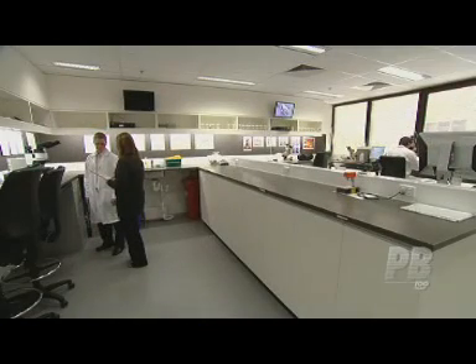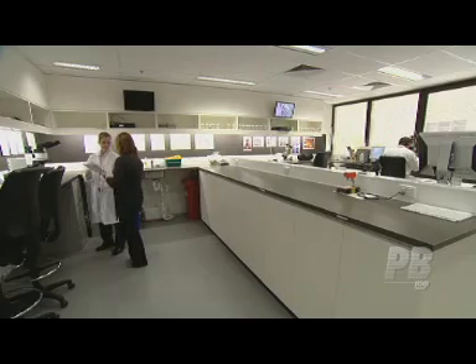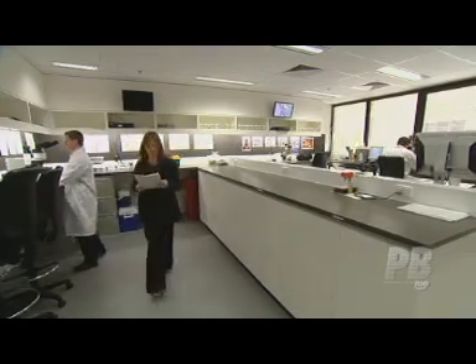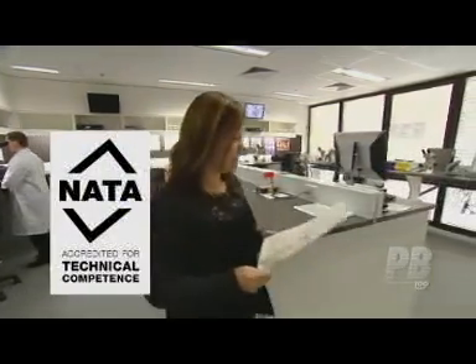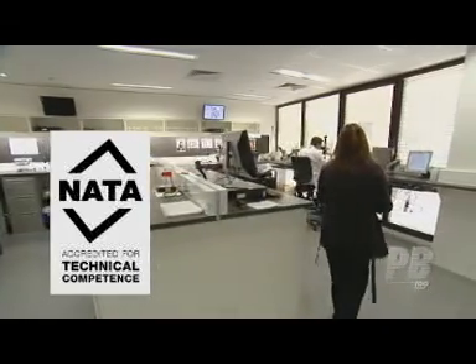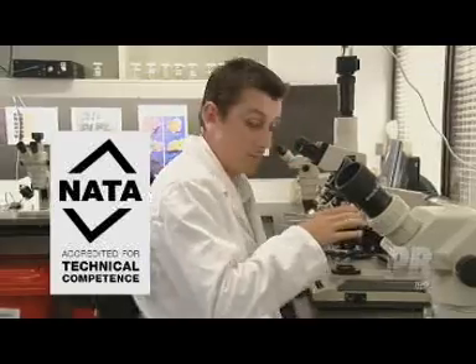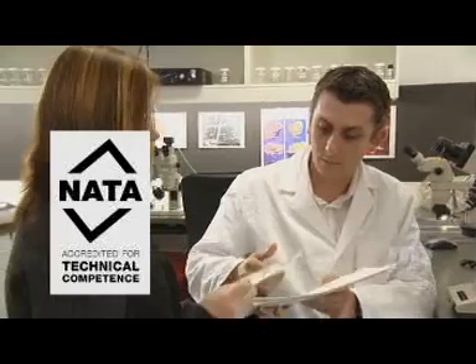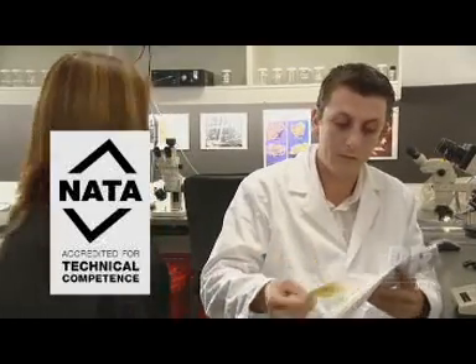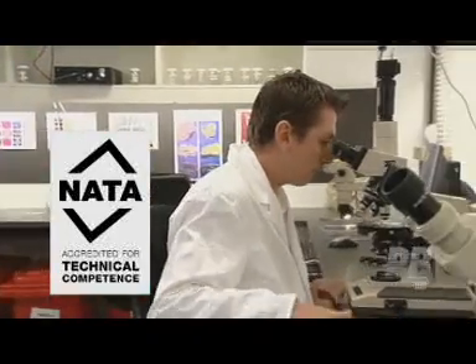To be certain test results are reliable and consistent, the sample analysis should be undertaken at a National Association of Testing Authorities or NATA laboratory. NATA-approved laboratories are required to follow specific standards and methodologies and are regularly audited for compliance.